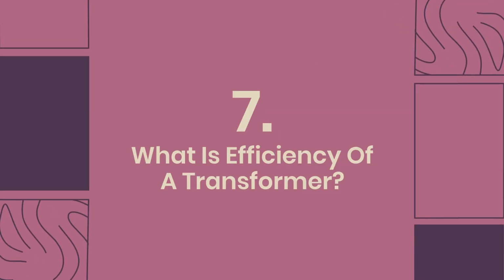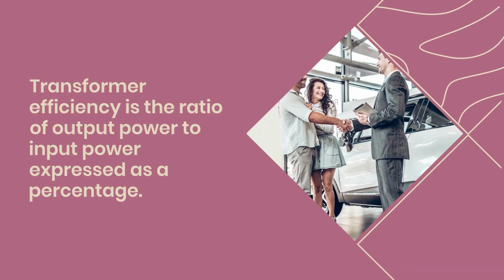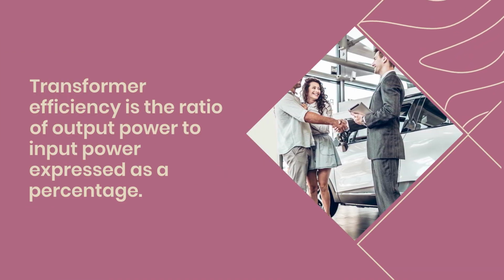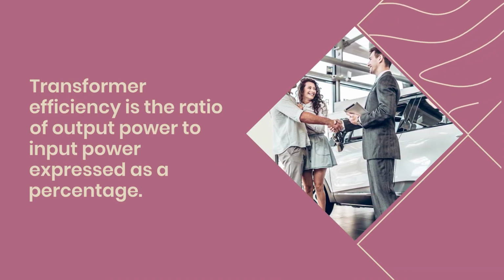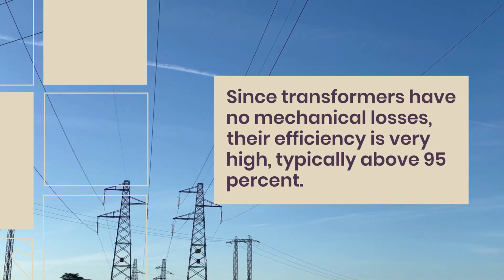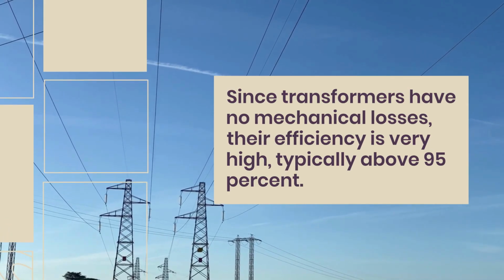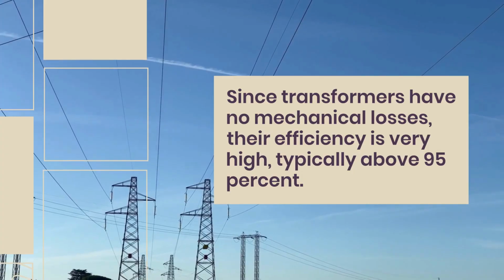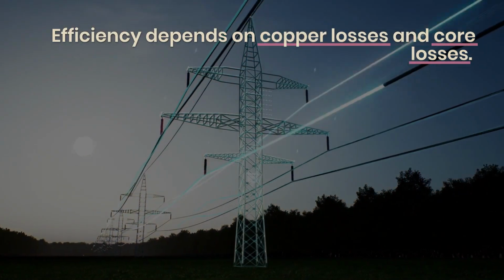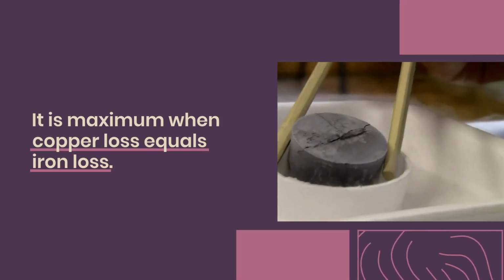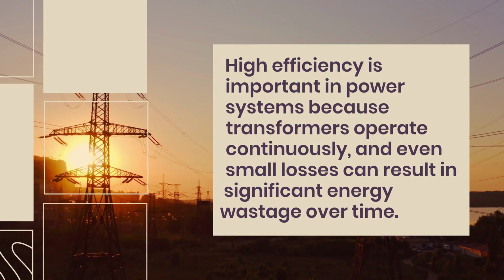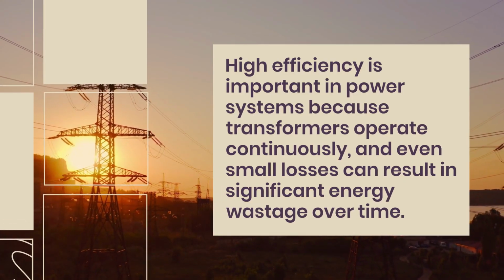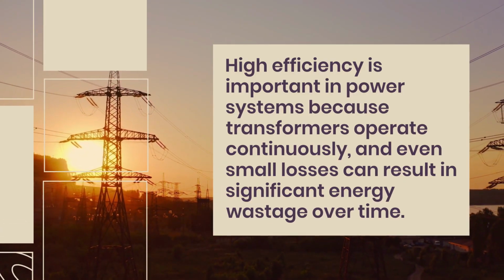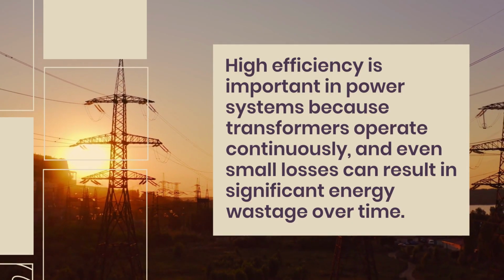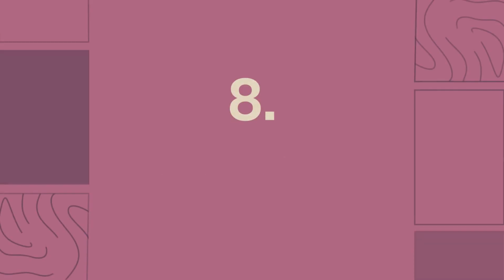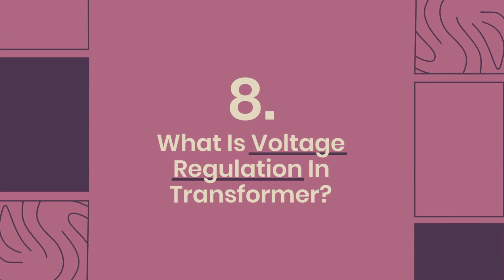7. What is efficiency of a transformer? Transformer efficiency is the ratio of output power to input power expressed as a percentage. Since transformers have no mechanical losses, their efficiency is very high, typically above 95%. Efficiency depends on copper losses and core losses. It is maximum when copper loss equals iron loss. High efficiency is important in power systems because transformers operate continuously, and even small losses can result in significant energy wastage over time.